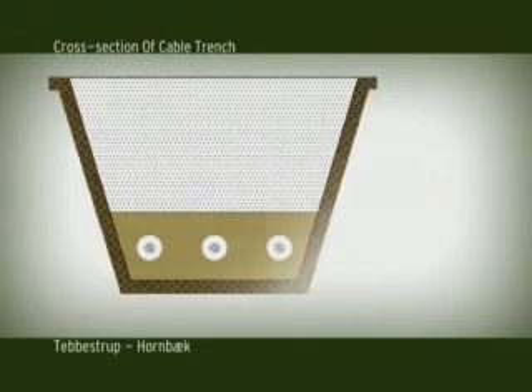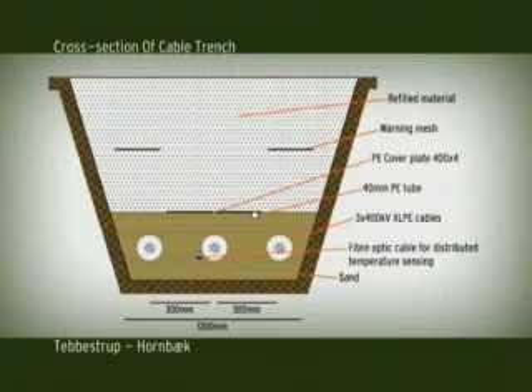The cables lie in a flat configuration with a phase spacing of 300 mm. The spacing between the 2 400 kV circuits is 6 meters. Besides the cables, empty pipes have been laid through which fibre optic cables have been flushed. The fibre optic cables can be used for telecommunications and in future for distributed temperature monitoring of the cables.